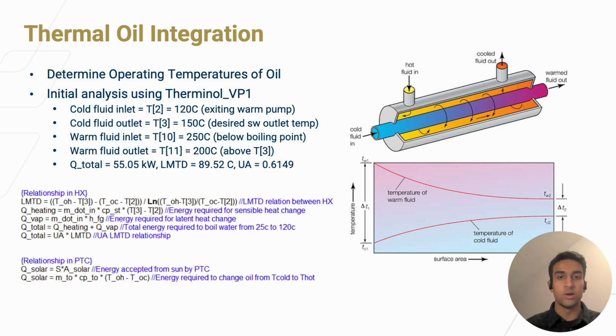We decided to make these predetermined in accordance with how a concentric counterflow heat exchanger works. So we used a cold fluid temperature of 120 degrees at the inlet, 150 degrees at the outlet, and a hot fluid temperature of 250 degrees at the inlet and 200 degrees at the outlet, which gave us the following Q, LMTD, and UA values.